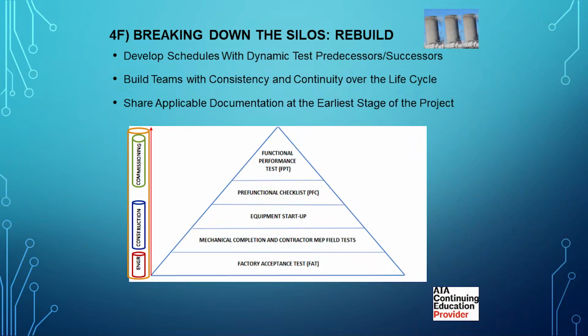So what you want to do, as I said before, in terms of change, is try to rebuild. If everybody's looking at your triangle, where commissioning is doing pre-functional checks, construction checklist items, and functional checklist items, the construction guys are doing their general QA, QC, MEP field tests, NETA tests, and working with startup, and the design folks, engineers, and owners are looking at factory acceptance tests.